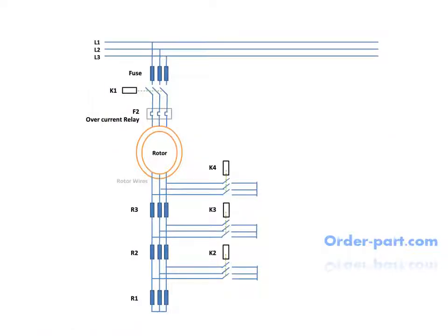Initially all contactors are open. To start the motor, K1 line contactor should be closed. You can see all rotor resistances are in series, meaning high starting torque. After 5 seconds, K2 contactor closes, which removes R1 resistance.